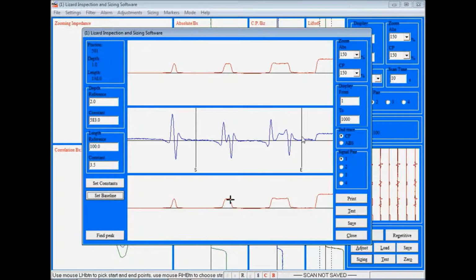Now, the only part of the length that I'm using is just moving the start and end cursors so that when I click find peak, the system will put the cursor to the highest amplitude of signal between this start and end. We do not need to know the length of the defect in order to generate the depth. So now if I click find peak, you'll see this cursor jump to the highest position between the start and end cursors. Oh sorry, I just moved the baseline slightly. It doesn't matter because we've already set the baseline, so it hasn't affected anything down here.